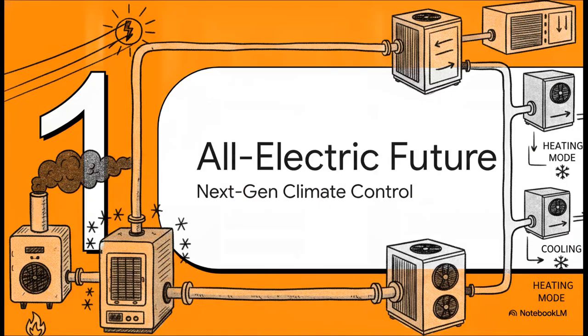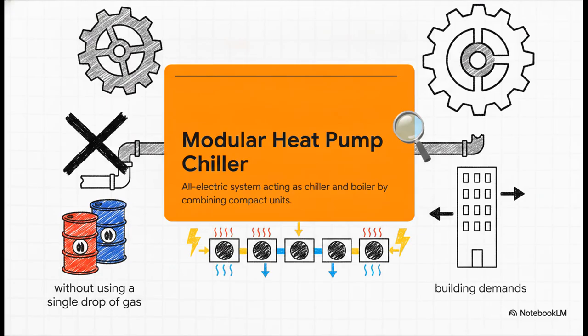Let's get to it. Section 1: the all-electric HVAC future, demystifying the next generation of climate control. Traditionally, big commercial buildings needed a massive gas-guzzling boiler for the winter and a completely separate chiller for the summer. It's just how it was always done. But a modular air-to-water heat pump chiller replaces those legacy machines entirely. It functions as both your heating and cooling source, without burning a single drop of gas. By linking up multiple compact all-electric units, it hits the exact load your building demands.